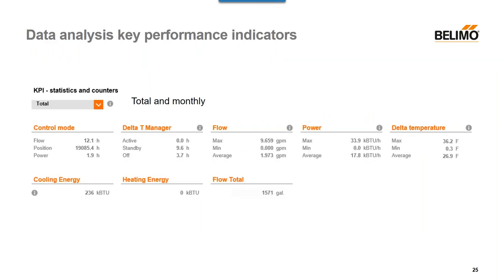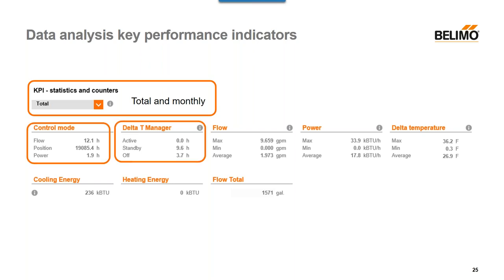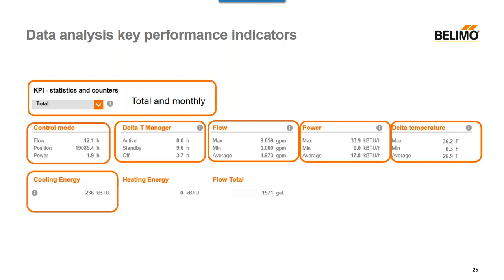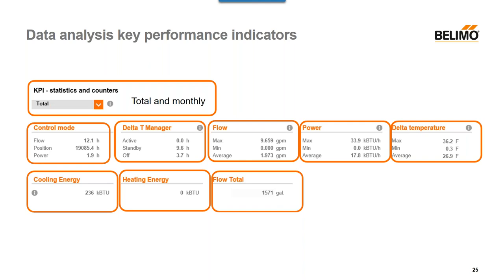There are also key performance indicators built directly into it that show, for example, how the valve is operating either total or monthly: what control mode it's in, how often the Delta T manager has been enacted, maximum, minimum, and average flows, same with power and Delta temperature, total cooling energy, total heating energy, and total flow being used. This really allows you to understand from an operational standpoint how the valve is operating.